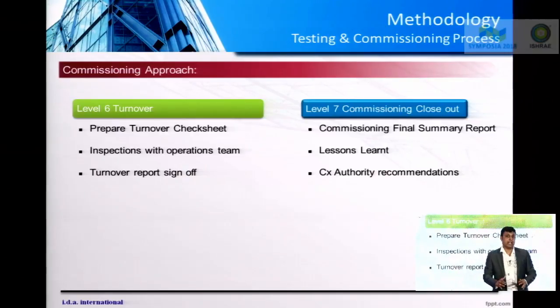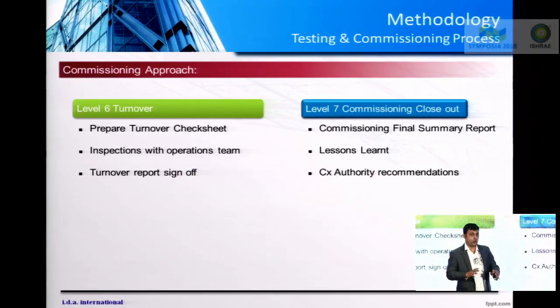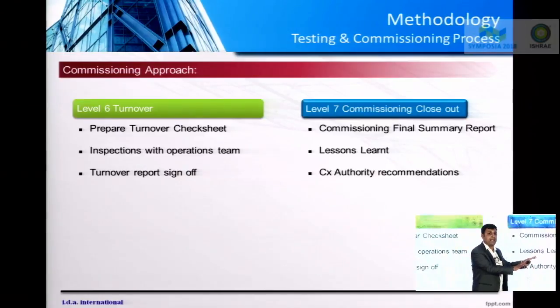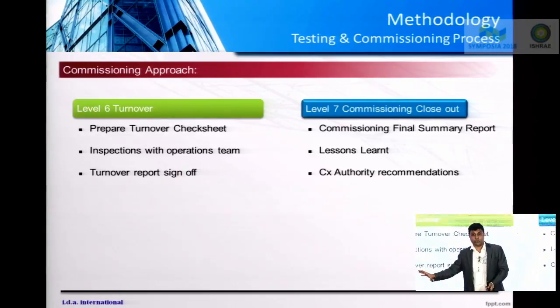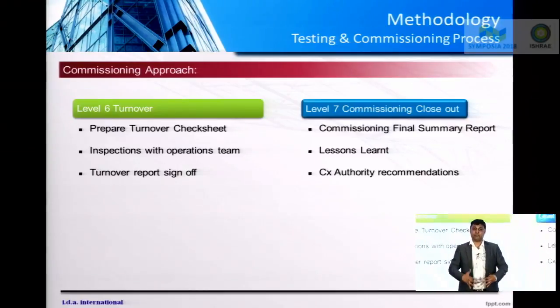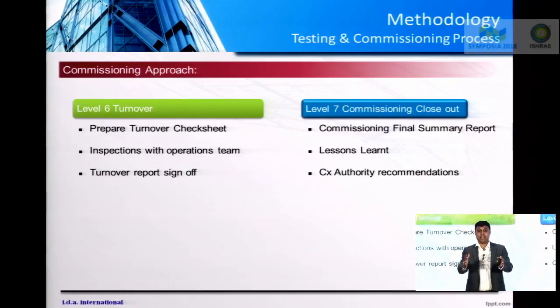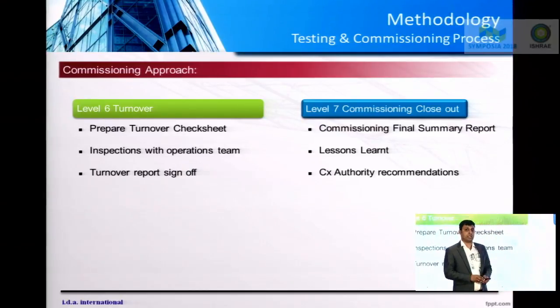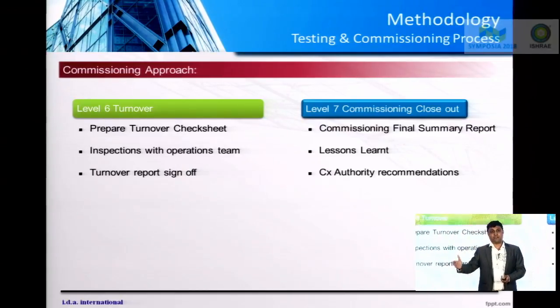You have to ensure that before you hand over the facility to operations, all the equipment is at its design conditions. All the breakers which are supposed to be normally open are normally open. All the breakers which are supposed to be normally closed should be normally closed. So that's level 6, an official handover to the operations team, and it has to be rightly documented. And finally comes level 7, which is commissioning closeout, which is the end of the project.